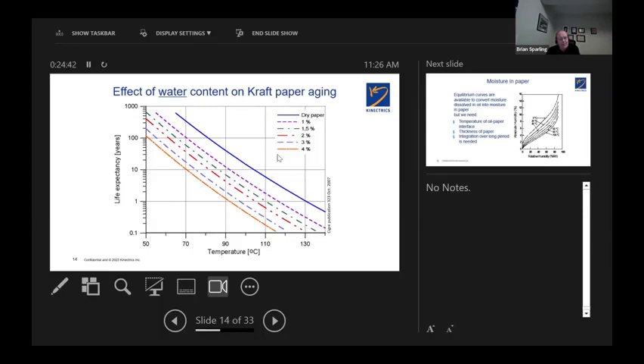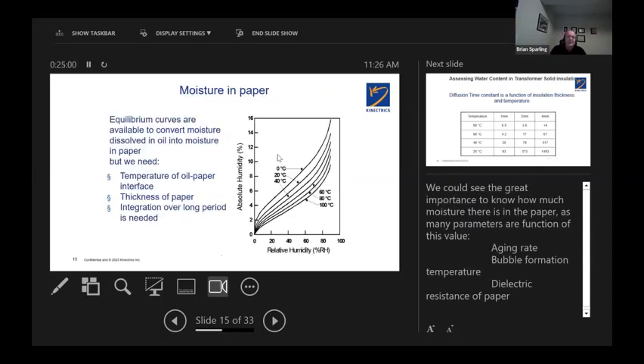But if it goes to 1%, it's going to be living half the life at 70 degrees C or 110 degrees C versus dry. So this gives another indication of the life of the transformer's active part in terms of the effective water content in the kraft insulation.